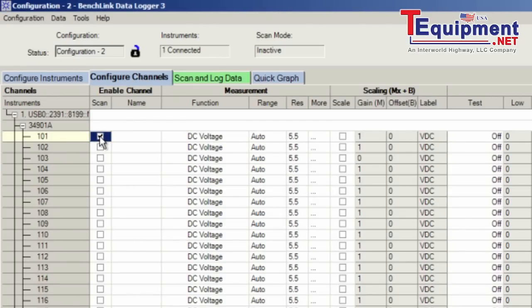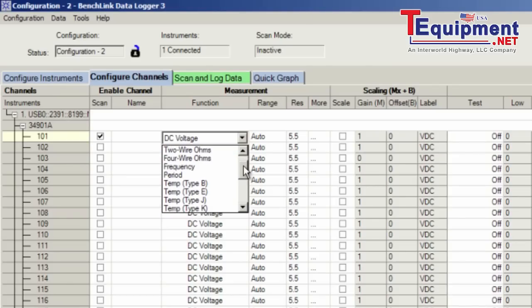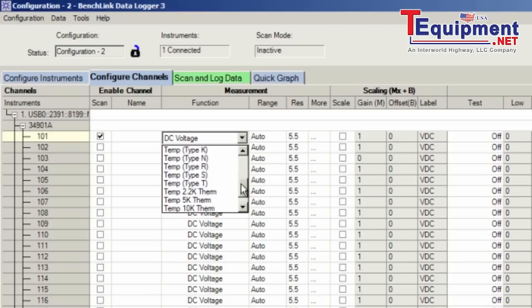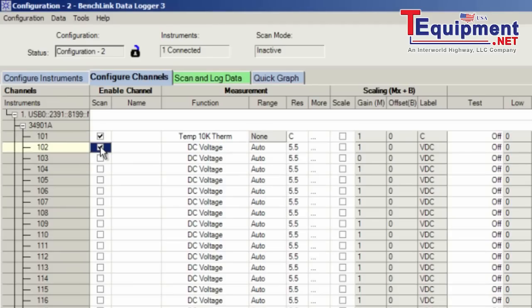On the first channel, I've hooked up a thermistor. The way the Agilent 34972 works is it uses a universal channel, so I can connect my DUT or sensor to any channel. Then in the software, go ahead and select what type of voltage, resistance, or frequency I should measure on that channel. I have a thermistor, so I'm going to scroll down and pick a 10K thermistor. So this channel is configured.